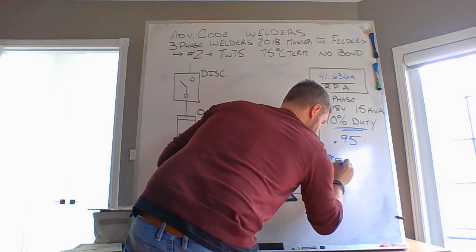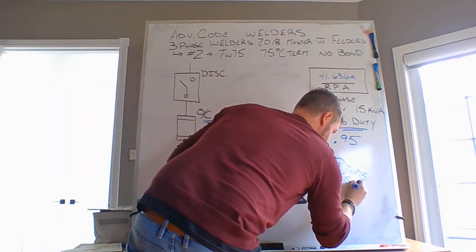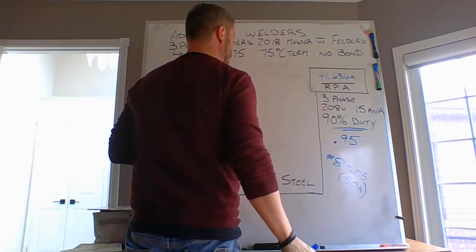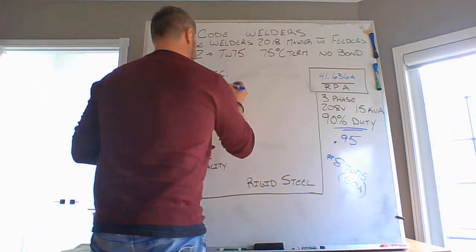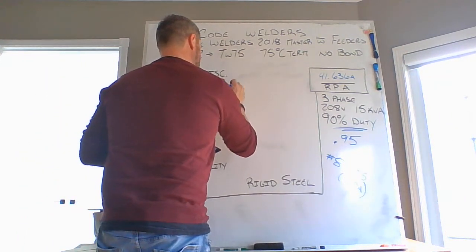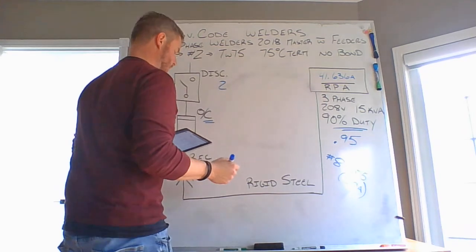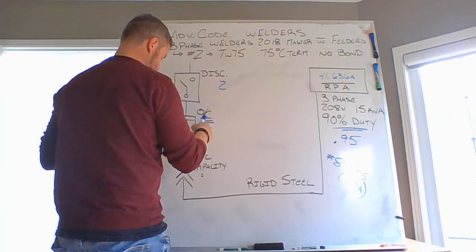Number 8, TW75, 50 amp conductors, or my rated primary current, 41.636. First calculation, you are looking at 200% of your rated primary current to determine your overcurrent device.